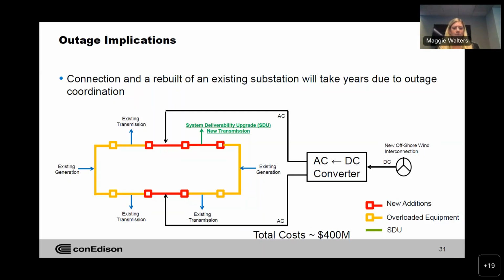As Walter mentioned, typically our outage scheduling season runs from September through May with additional limitations through the winter season. Multiple elements in an existing substation cannot come out of service at the same time due to reliability considerations. Therefore, to execute all the upgrades seen here could cost around $400 million and could take a decade to complete.